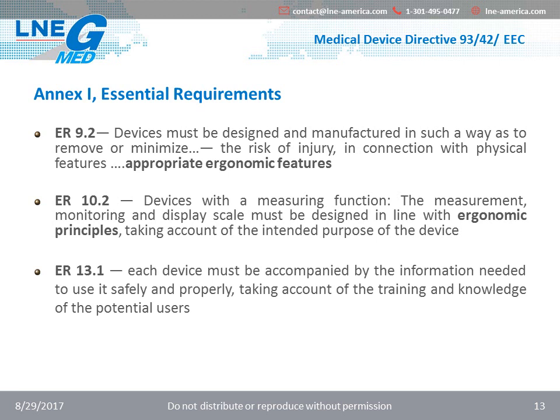Essential Requirement 13.1 mentions each device must be accompanied by the information needed to use it safely and properly, taking account of the training and knowledge of the potential users. Other essential requirements that are affected by usability are number 2 through 6, 11.4.1, 12.8, and 12.9.